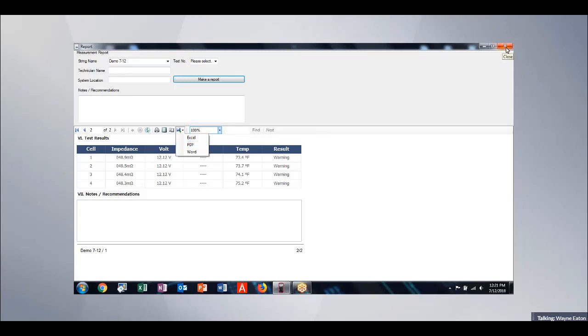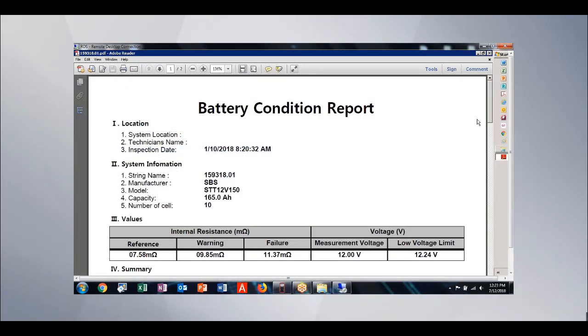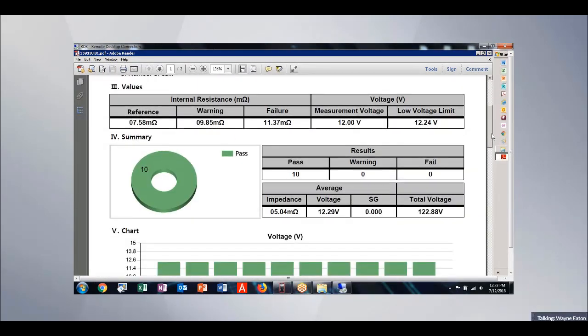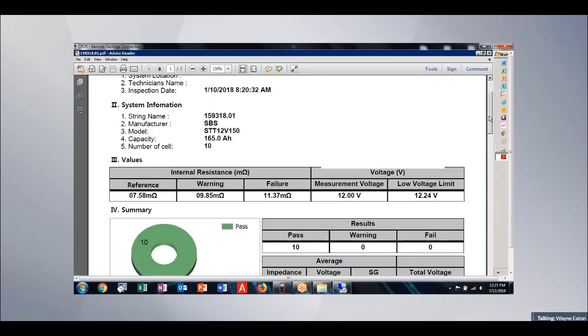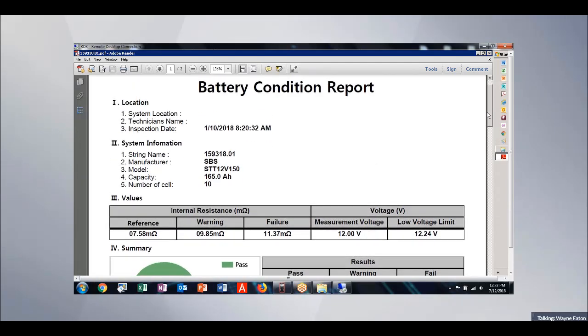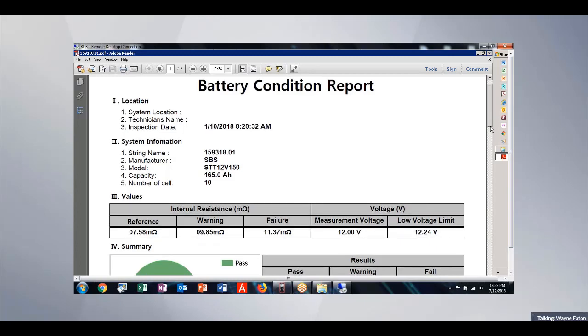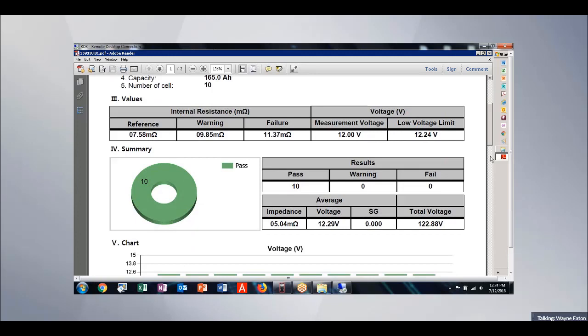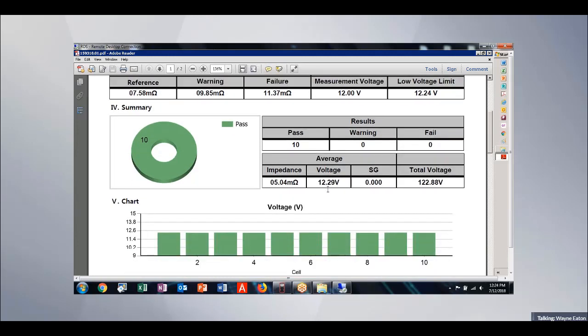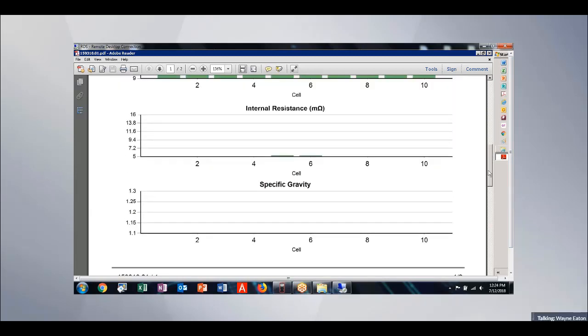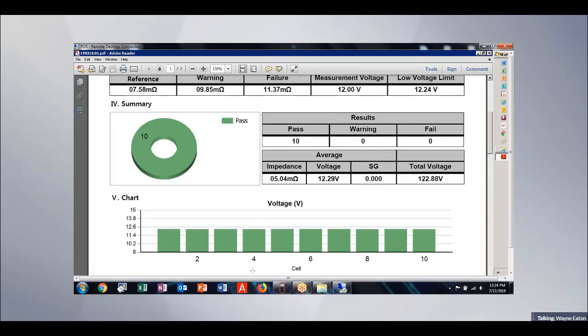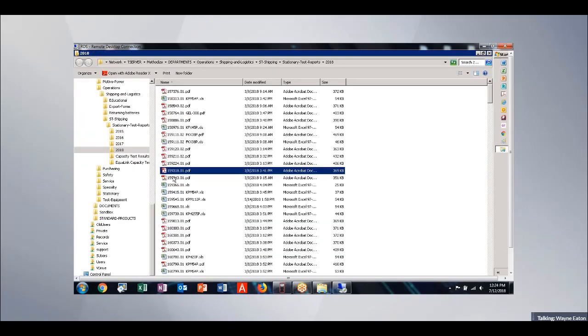So once I start generating reports with the unit, your quarterly or monthly battery reports are going to come in this format, and as often as you do your maintenance, it's going to give you a battery condition report. It's going to give you the reference values, the measurement voltage, what that low voltage limit was. It's going to give you the number of cells that pass, fall into warning, or fall into failure. And then it's going to give me all the averages. The bar graphs themselves are going to show the plotted trends or differences in voltage between the cells, internal resistance between the cells, and specific gravities.